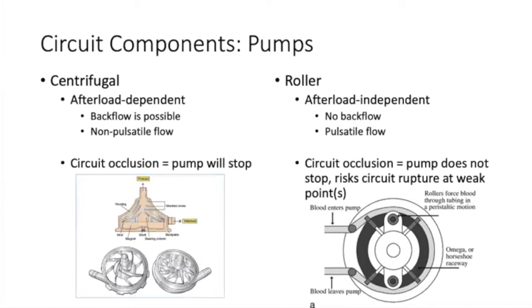Regarding the pumps: for the main pump on the circuit, we almost always use centrifugal pumps. These are afterload-dependent, meaning the flow generated depends on the afterload against which the pump is pumping — the same as an ECMO pump. So counterintuitively, if there is higher pressure, pump flow will go down.